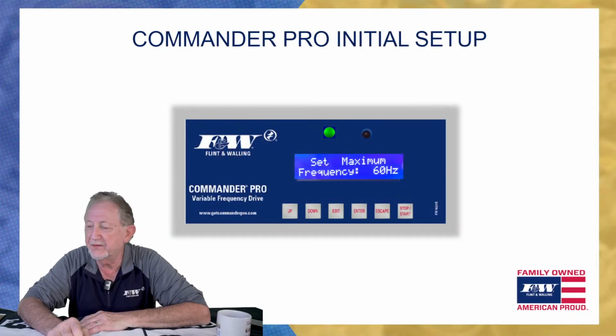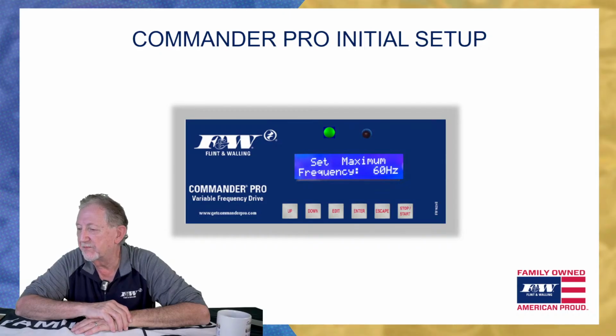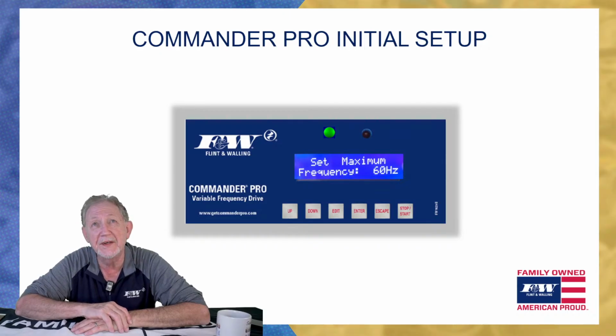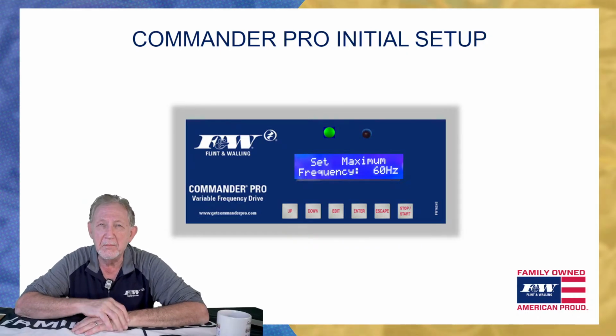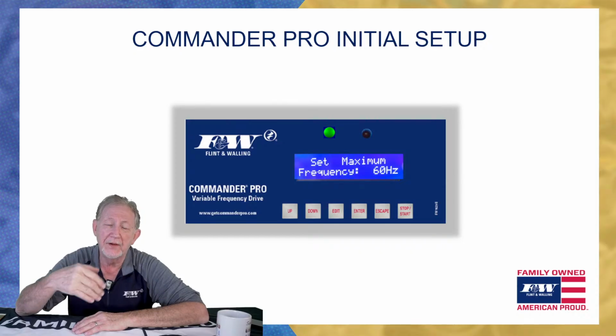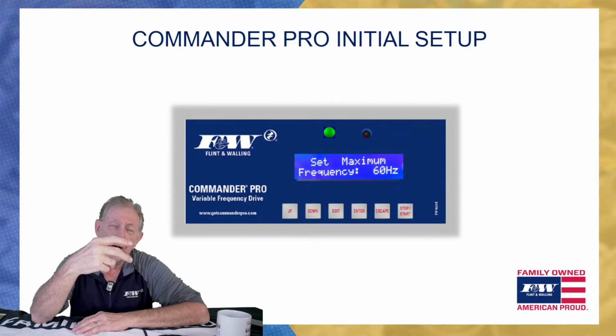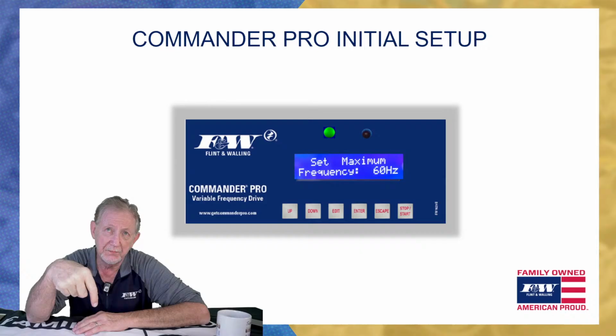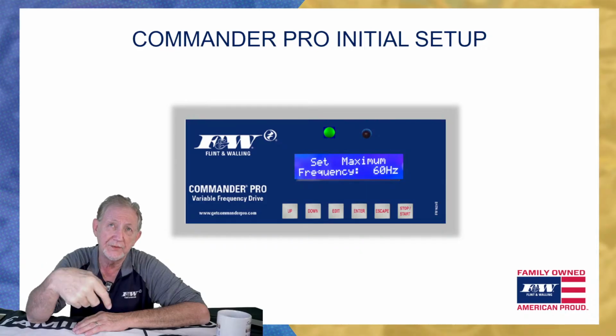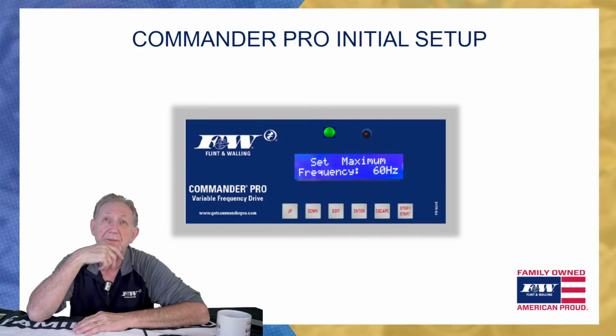Maximum frequency, all right? So here's where we can set maximum frequency. This maximum frequency is showing 60 hertz. You would run 60 hertz if you were running a matched pump and motor. In other words, the pump end by horsepower is matched to the motor by horsepower. So you've got a matched pump and motor horsepower.